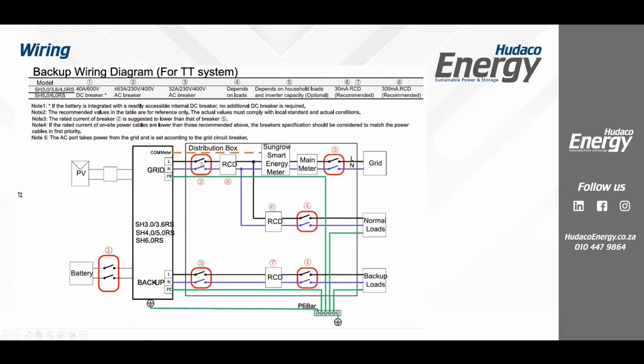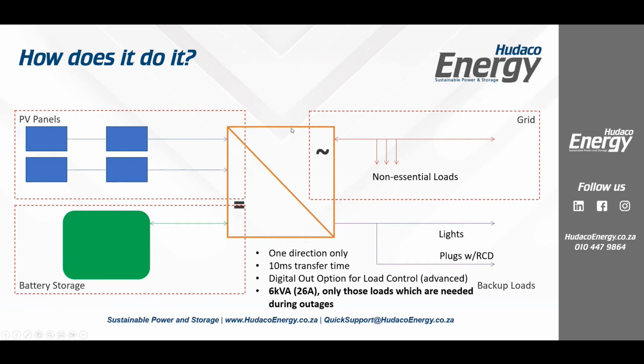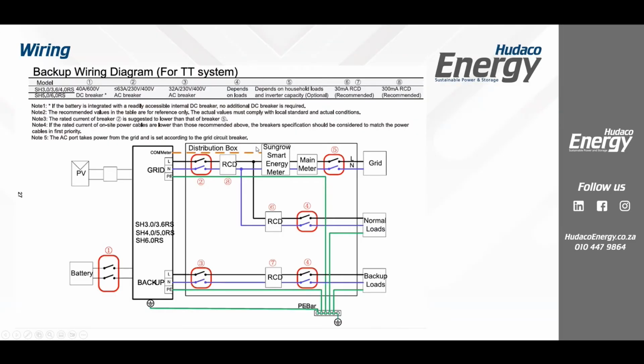You might have your feed to your breaker, and this is where we recommended a 63 amp breaker here with a 10 mil cable going into your inverter. If you have a look, this is just an electrical diagram of what I've shown there. Okay, here's your inverter. Then on your backup port, we recommend having earth leakage there as well. In my drawing, I showed this being split with lights coming off, let's call it this way, without RCD. But on your RCD side, please, you just need to have protection for compliance so that when we are in a state of load shedding or grid disconnection, your plugs that are on your backup port are still protected, right? That there is earthing in place there.